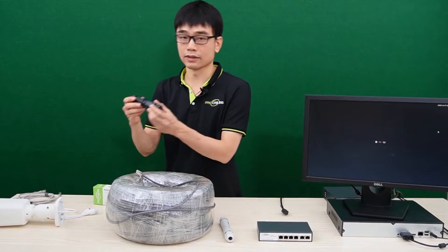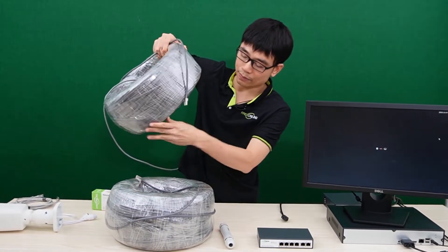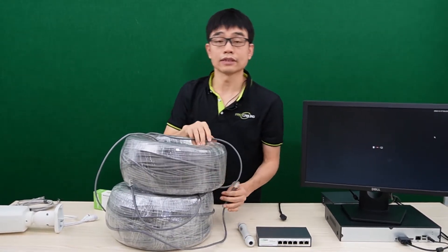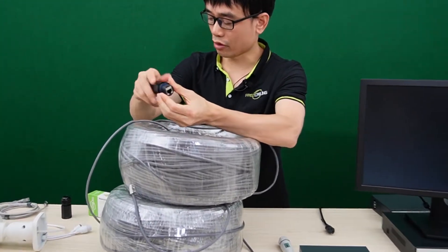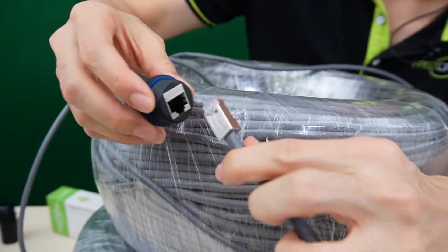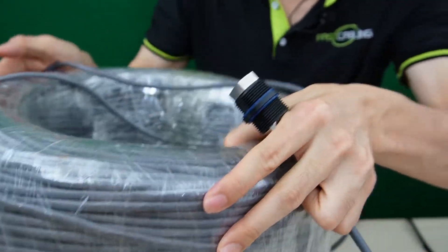The problem is I cannot get any cable beyond 1,000 feet, so I have to use this coupler to chain another spool of cable. Eventually, we got 1,600 feet. This is just a waterproof coupler — it allows me to join two cables together to get 1,600 feet.